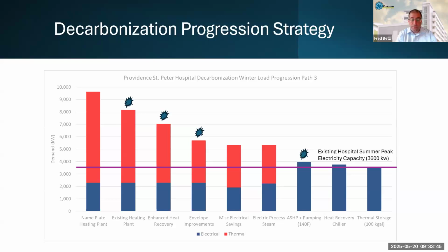Okay, so now we've done all those demand side measures. We've reduced the load through a variety of ways, and now we're finally getting to our heat pumps here, so we can right size those heat pumps. Which again, with that COP of about 1.6, 1.7, we are able to get us down to just under 4 megawatts of capacity. But we're falling short. So we got to keep going.